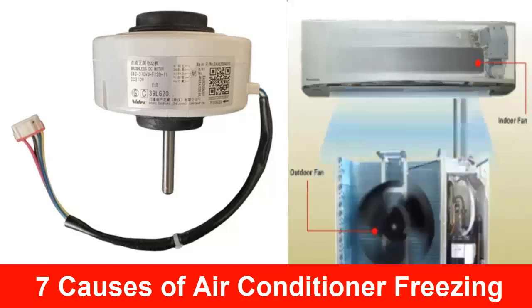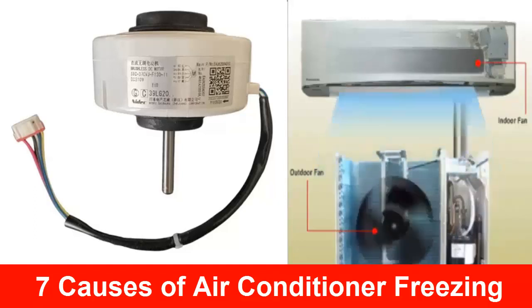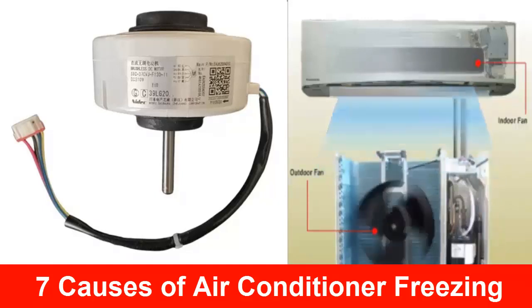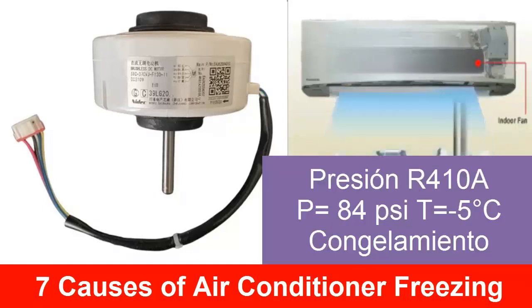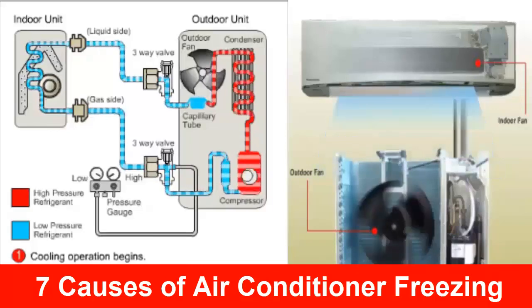4. Insufficient airflow from the evaporator turbine. Because the motor is rotating very slowly, there is less airflow, therefore less heat, the pressure of the evaporator drops, and its temperature as well, causing freezing. You must check the capacitors, bearings, and the condition of the fan.